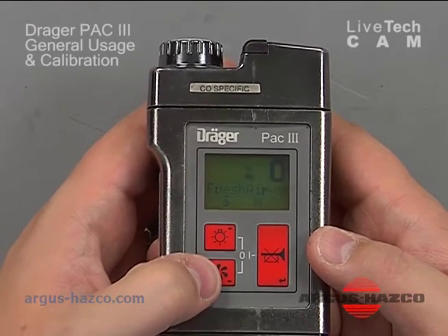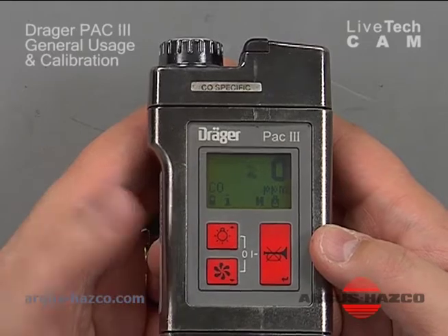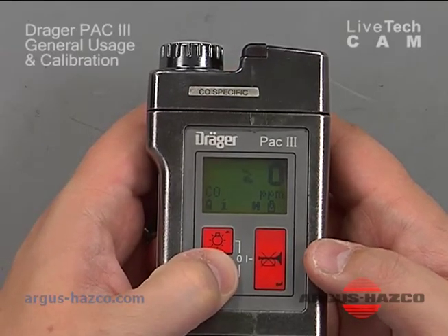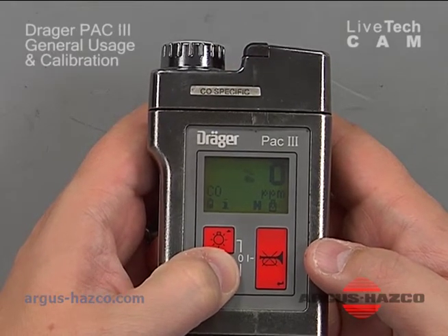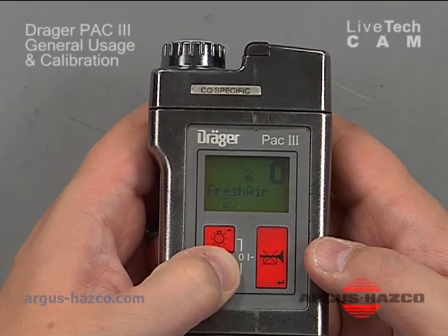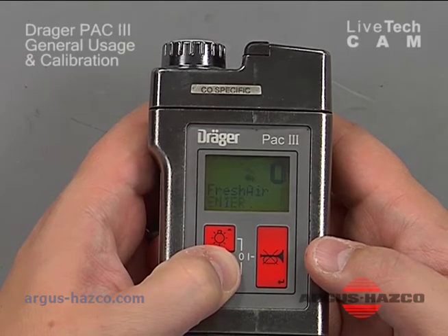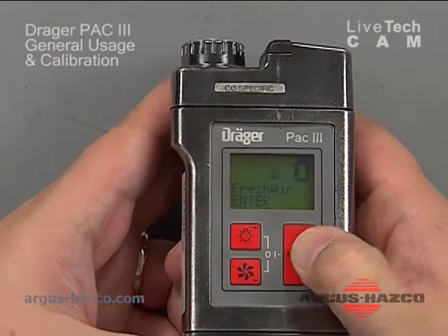Then it'll say fresh air, start counting down. If you didn't want to do it, you let go. If you want a fresh air 0, you just keep holding it through the countdown. At the bottom it says fresh air 3, 2, 1, and then you just enter, and it does a fresh air 0.